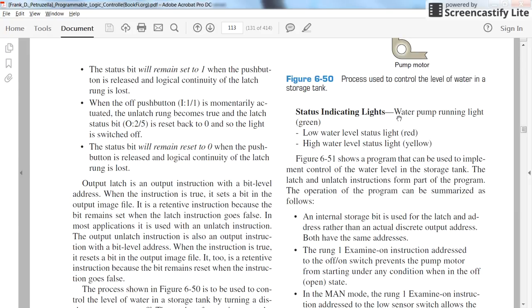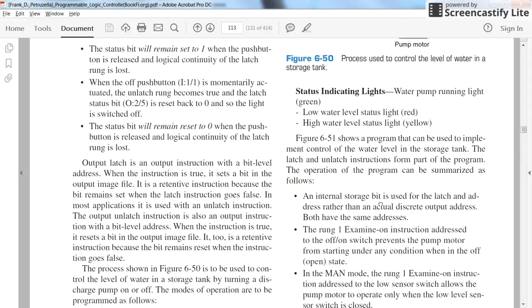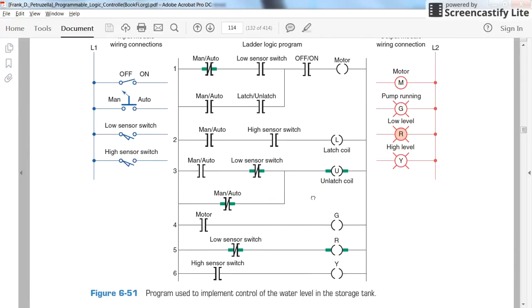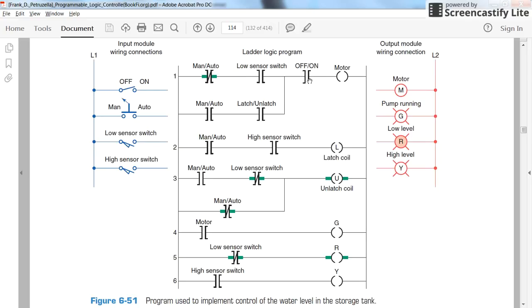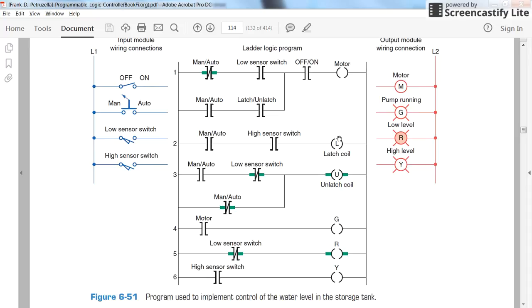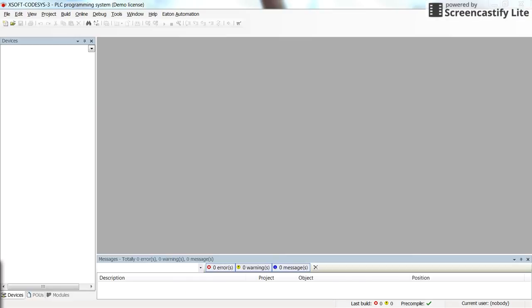We have the status indicating lights — green, red, and yellow — as already discussed. Here we have the explanation for the ladder logic program and the ladder logic program itself. We have contacts and coils, some referring to the pilot lamps, one coil for the motor pump, and some internal variables which can be latched or unlatched. The corresponding contact is used in series with the manual or auto switch.